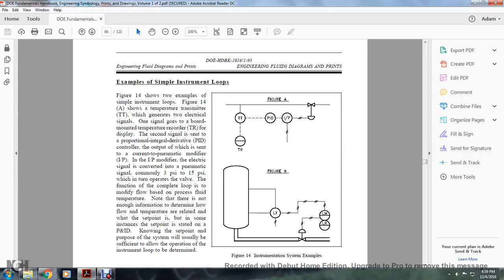Simple Instrument Loops: Figure 14 shows examples of a simple instrument loop. Figure 14A shows a temperature transmitter TT that generates an electrical signal sent to a board-mounted temperature recorder TR for display. A second signal is sent to a PID (proportional integral derivative) controller, whose output is sent to an I/P pneumatic modifier. The electrical signal is converted to a pneumatic signal — commonly 3 to 15 PSI — which is used to operate valves and modify flow based on process temperature. Note there is not enough information to determine how flow and temperature relate to the set point.